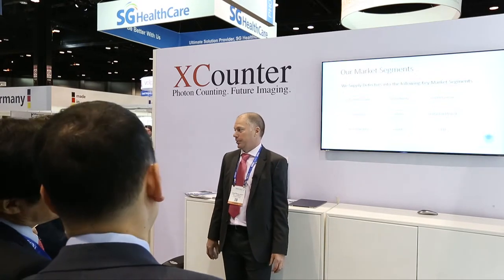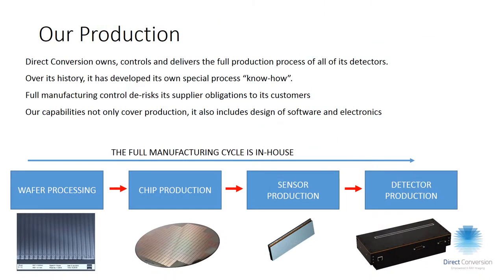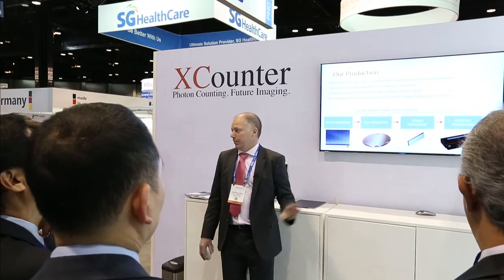The conversion efficiency isn't great at those energies, but the position accuracy we get from the detector is still very good. We control the whole chain from developing ASICs ourselves — we don't produce them, we buy wafers from TSMC — then do our own processing to grow bumps on the wafers, dicing, bump bonding, automatic die placing, and wire bonding to form the detectors.